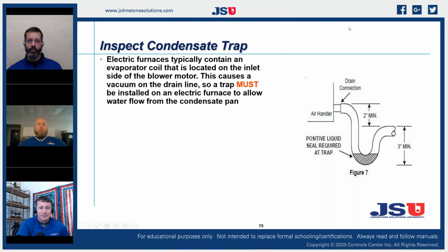Great point. So I've actually, complete side note, I've actually seen a plugged heat exchanger, or starting to go plugged, and the inducer motor produced enough negative pressure that it sucked the condensate trap dry. So I've actually been having kind of an issue with that. On our condensing furnaces, we have what's called a front cover pressure switch. And a lot of manufacturers are using a front cover pressure switch. When you read the installation manual, you're required to put a vent on your standpipe for your furnace.